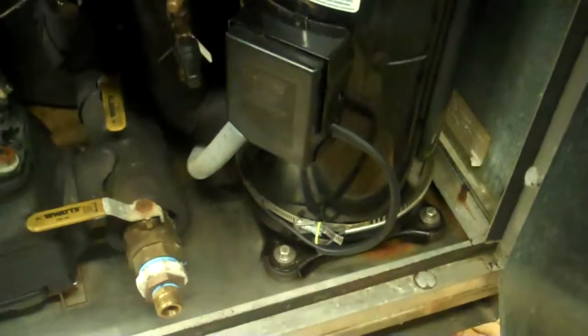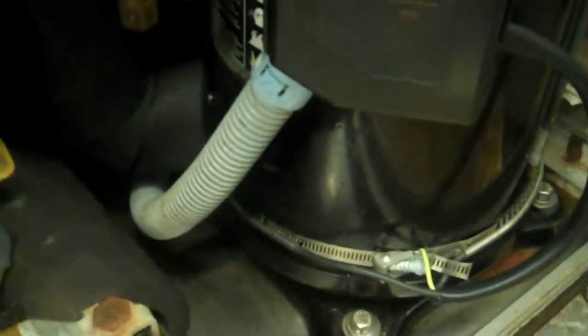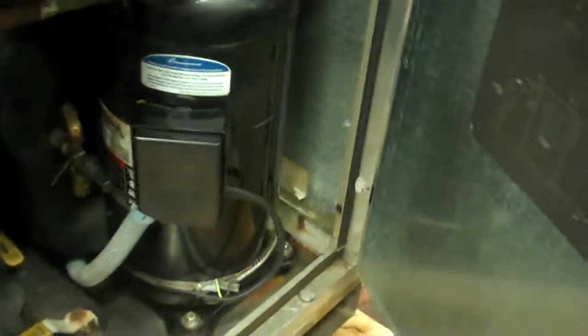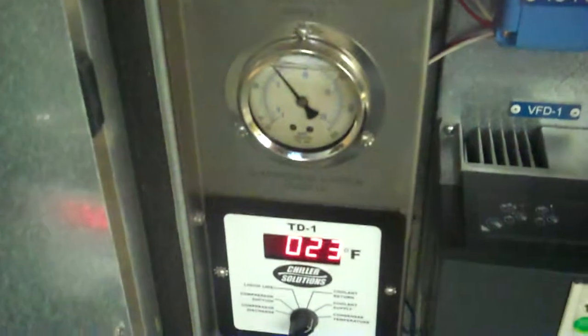And it is a Copeland scroll compressor, 7 horsepower. I think another thing we did on this one here is notice that there's a crankcase heater. I think we replaced that one. That's also something you want for an outdoor application. So a lot of nice little features this unit has. So you heard it kick back on, which is great.